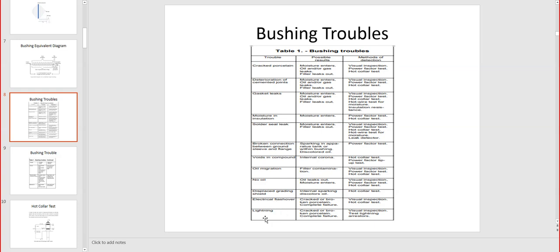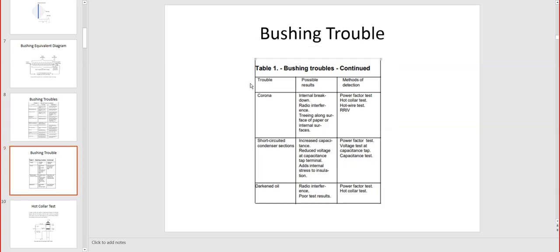Also you can have lightning discharge that goes to the bushings partially, even though you have surge arresters. Some of that energy may go through the bushing, so it may actually stress the bushing further, abnormally. Corona is very visible when you have some initial discharge between the bushing and the ground. Actually it is a little bit of a current, as a UV, like a light. The camera will catch that and it is traveling pretty much along the external part of the bushing. That's why you have the skirts, to try to block those leakage currents that are traveling on the surface of the bushing to the grounded tank.